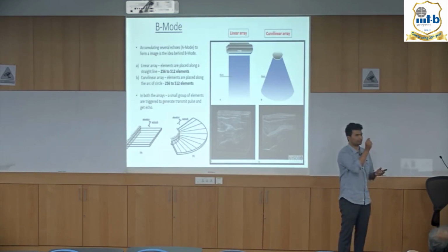10 to 15 elements are fired at the same time, so that we get an ultrasound pulse and an echo is received. This is done for all the adjacent sets of 15 elements. So you get 10 or 15 or 20 different echoes, and they are arranged side by side to form an image, where the amplitude of the echo is proportional to the brightness of the pixel.